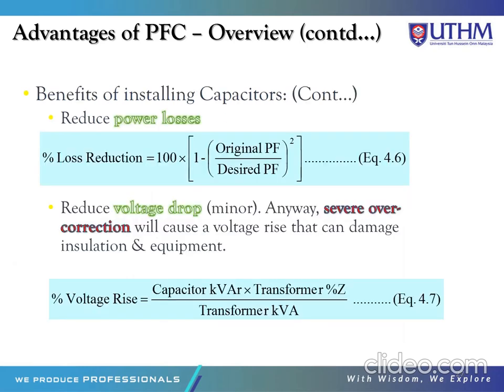Next, the benefits of installing a capacitor. The first one is that it can reduce the loss. This is the formula to calculate the percentage of loss reduction. This is the original power factor based on the actual load, and this is the desired power factor, the new power factor that we want. By using equation 4.6, we can calculate the percentage of loss reduction.